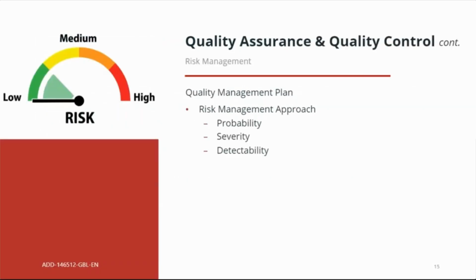Further, a robust quality management plan not only describes the statistical QC methods that were selected, but it also documents the risk management approach used to develop that QC strategy. So we evaluate probability, meaning how likely is the failure to occur, severity, how severe is the potential harm to the patient if the failure is undetected, and detectability, how reliably can our selected QC strategy detect that failure. And by limiting the frequency and severity of out-of-control measurement conditions, we ensure our role in preventing patient harm.